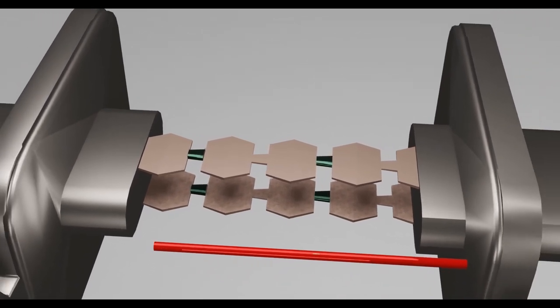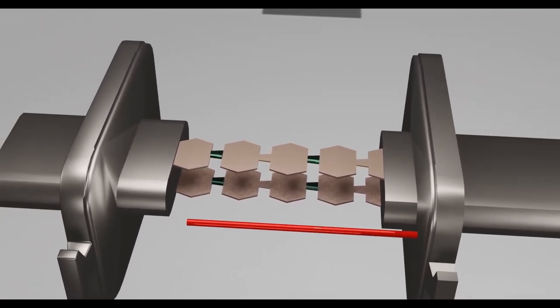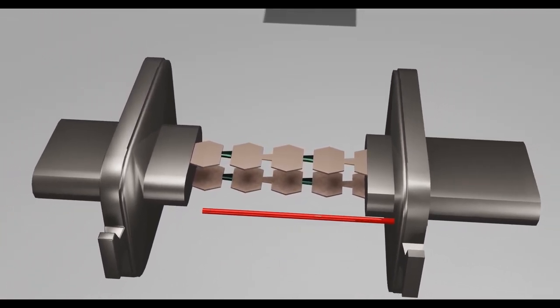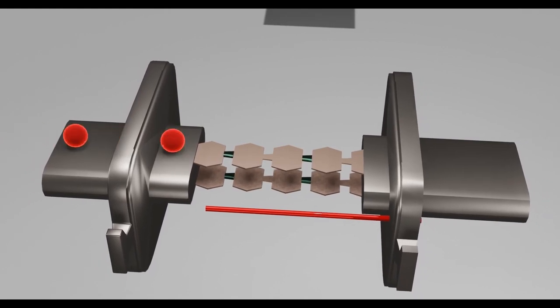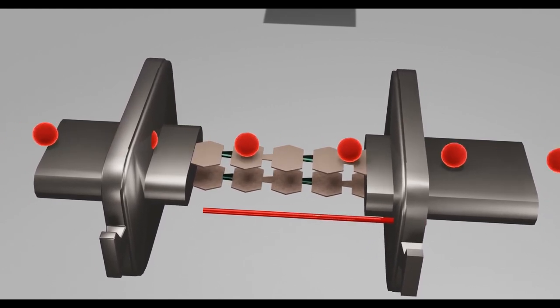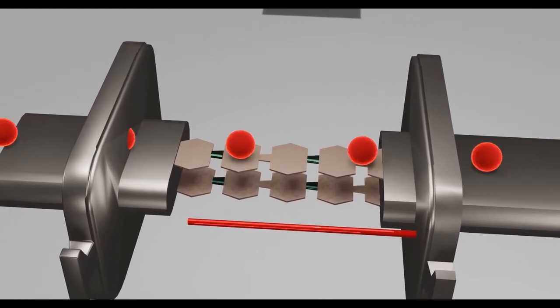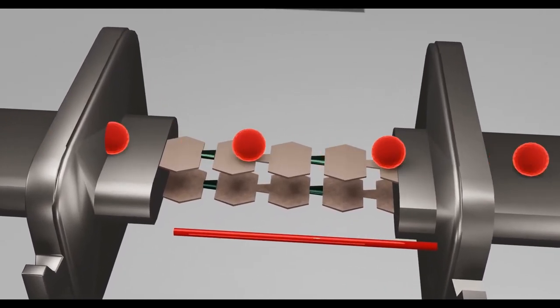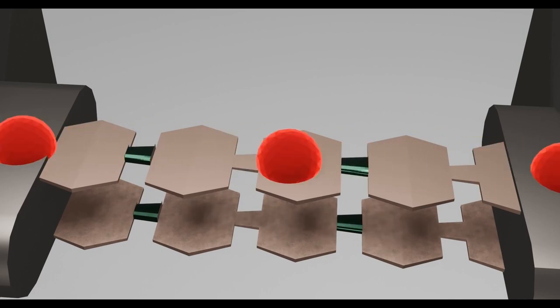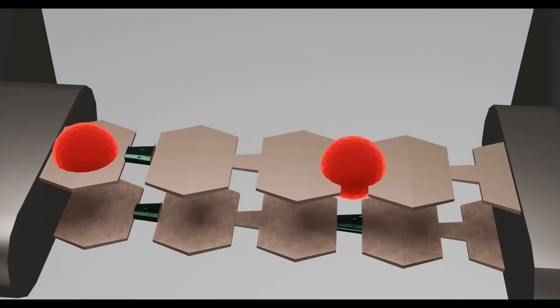occurs at the load side, such as a short circuit or earth fault, which leads to a very high amount of electrical current flowing through the fuse. This high amount of current flow through the element leads to development of thermal and heat energy.